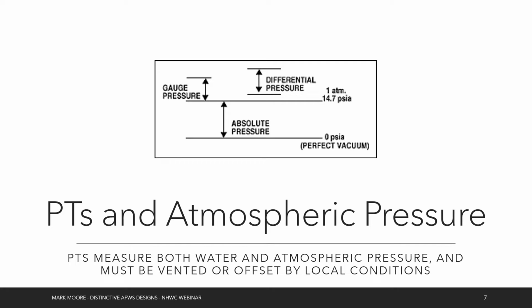There's kind of an issue with that, and that's PTs are measuring all of the pressure. A PT isn't just measuring how much water pressure is on it. A PT is actually measuring the water pressure and the atmospheric pressure above it. And so when we take these measurements from pressure transducers, something we have to be aware of is that we want to make sure we're canceling out the changes of the atmospheric pressure. And there's two ways you can do that. One way is you can put a vent tube behind the diaphragm, and that way any atmospheric pressure that comes from one side is canceled out by atmospheric pressure on the other side. Another way to do that is to have a separate barometric pressure sensor close to your gauge or inside your gauge, and then you can do that on your data logger and subtract the atmospheric pressure from whatever your pressure transducer read.